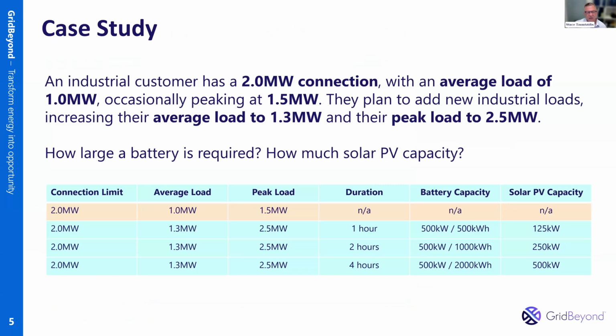So in this example, we've got an industrial customer with a 2 meg connection. His peak is 1.5, so everything's operating. There's no need to install a battery or do a network upgrade, but he puts in a new production line and his average load increases to 1.3, which isn't the problem, but his peak load is the problem, increasing to 2.5. So one option is to introduce a new transformer. That may or may not be possible depending on where on the grid he's connected. He may not even get a connection approval to go to 3 meg or 4 meg.